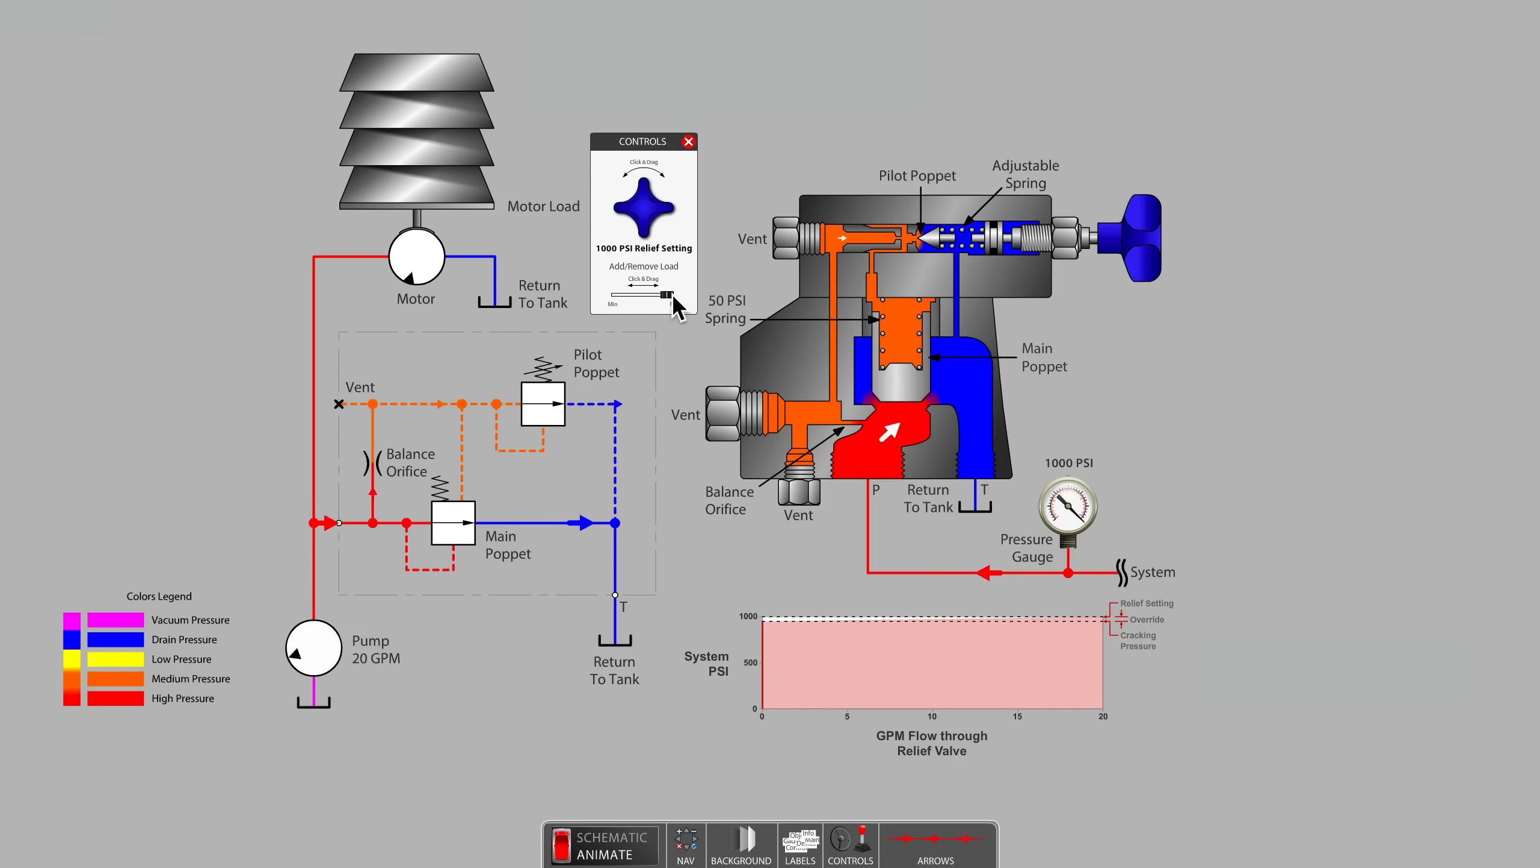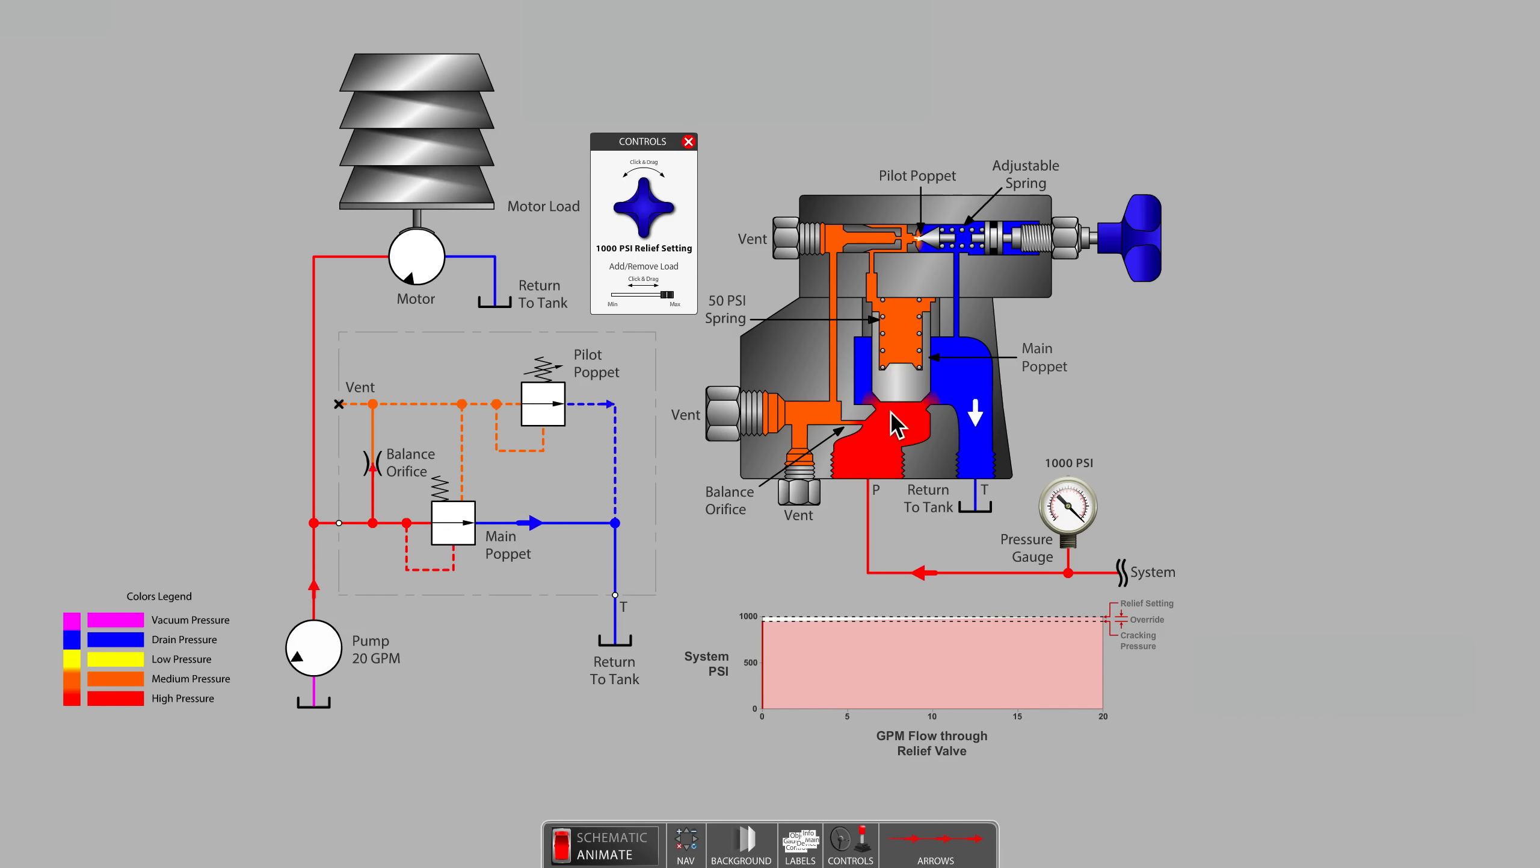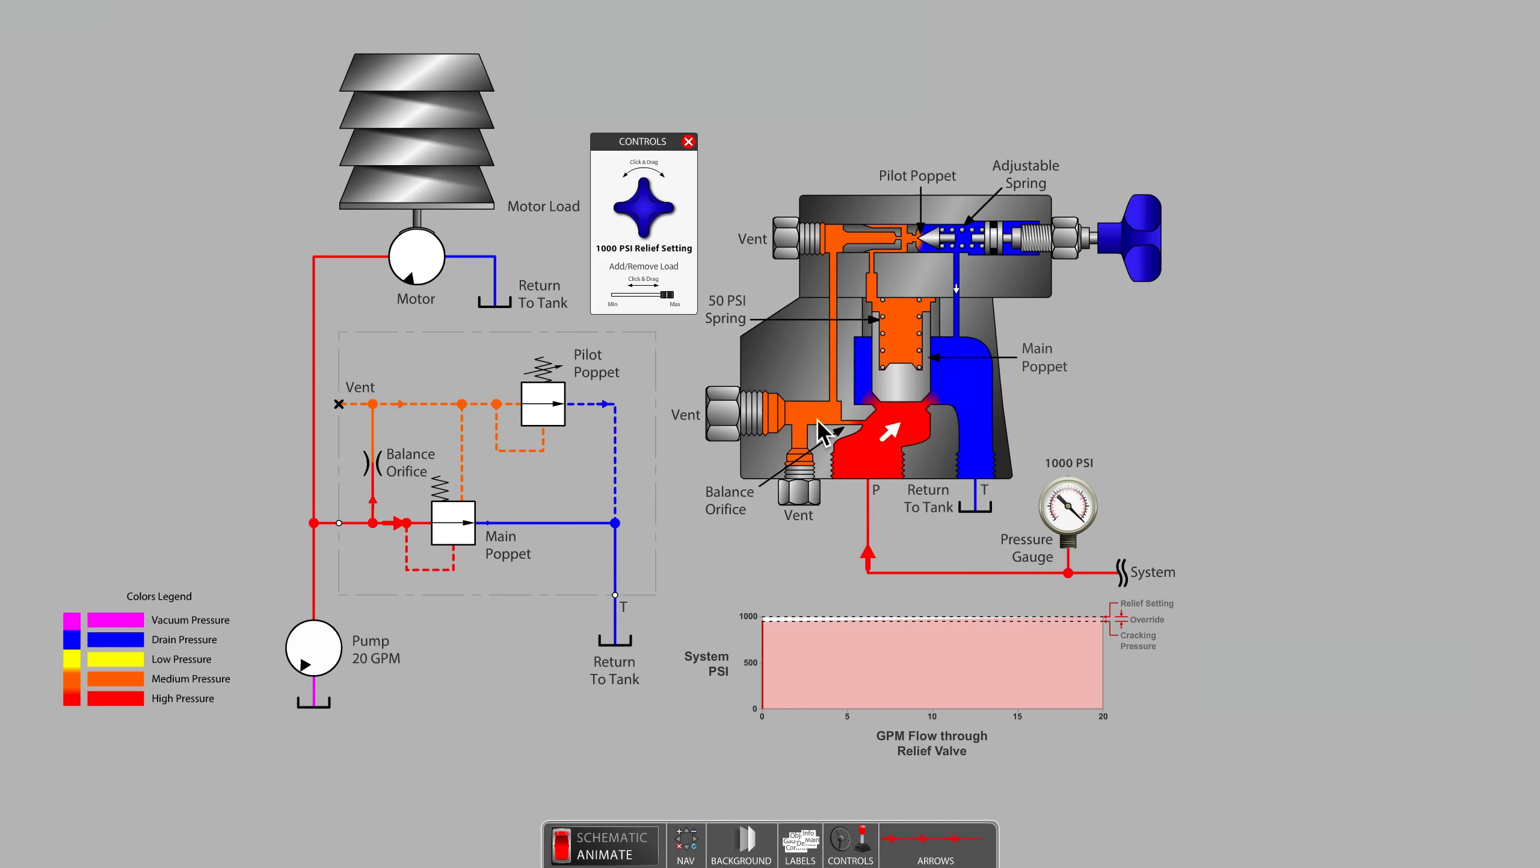The main poppet opens up by an amount based on the pressure imbalance above and below, due to the pressure drop that occurs as oil passes through the balance orifice and then onward through the pilot poppet.